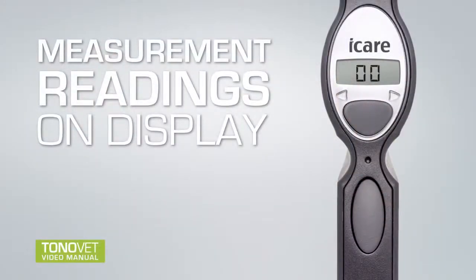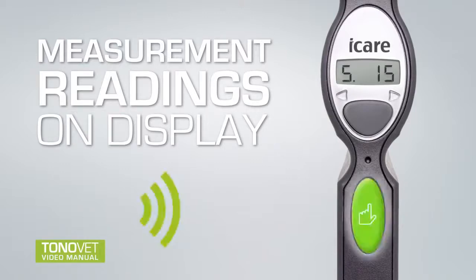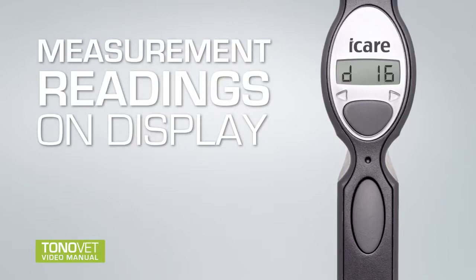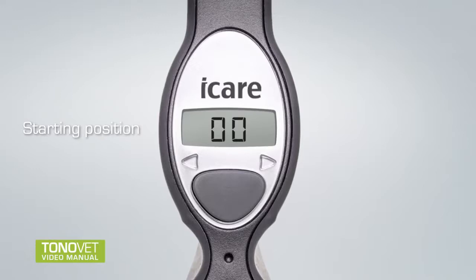Measurement readings on display. A single beep is played after each successful individual measurement. After the 6th measurement, a longer beep is played and the final result is displayed. Final result is an average of 4 middle single results. Measurement values during the measurement represent average values of previous measurements, not individual measurement values. 0, 0 on the display means the tonometer is ready for measuring.